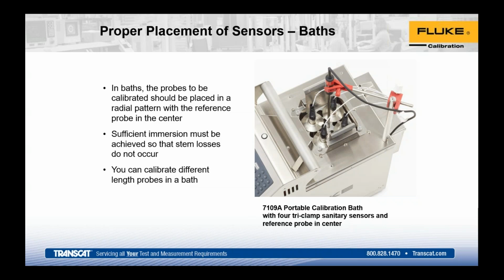Some folks will also, because of the fluid, add what they call lag blocks to add some additional mass. It's just a block of metal, like a dry well insert, in the bath that allows for more thermal mass. If you add mass, it's slower to change with fluctuations in baths. So again, there are workarounds depending upon what you're doing.